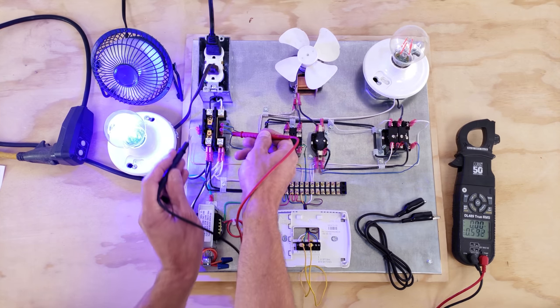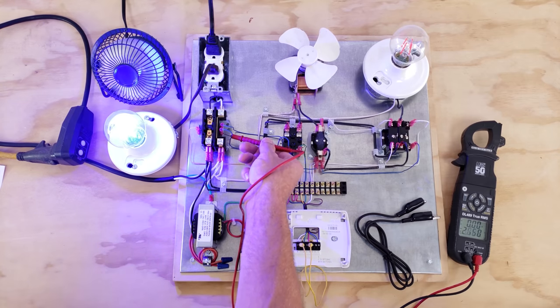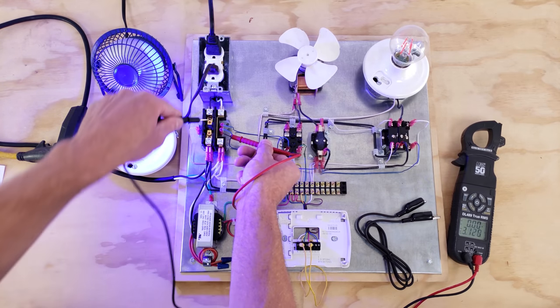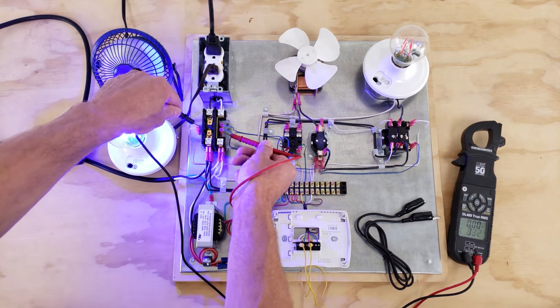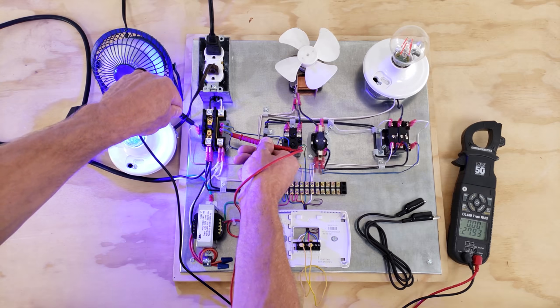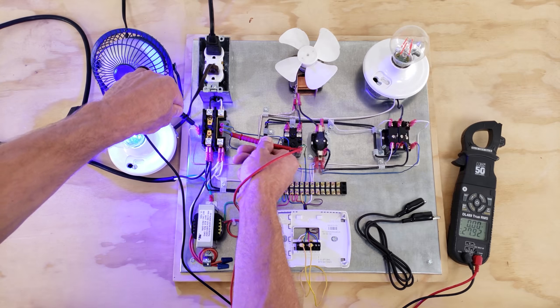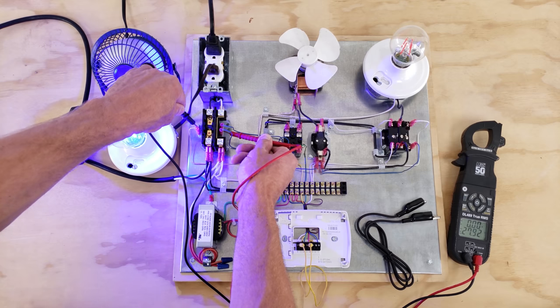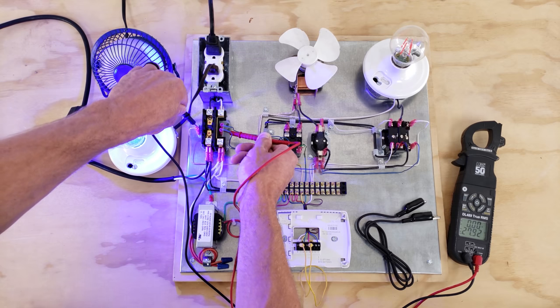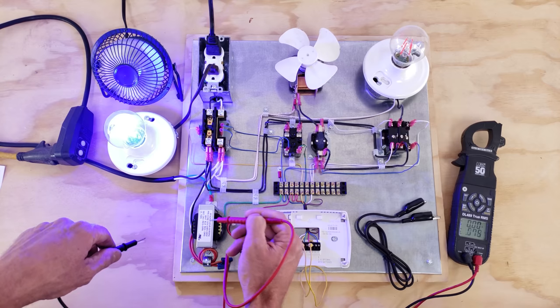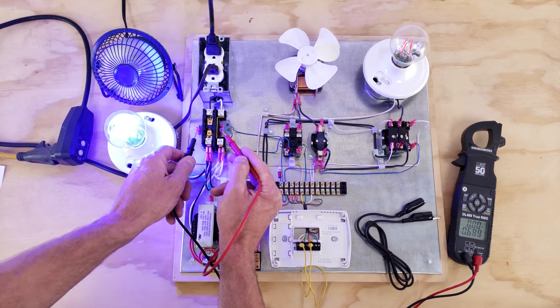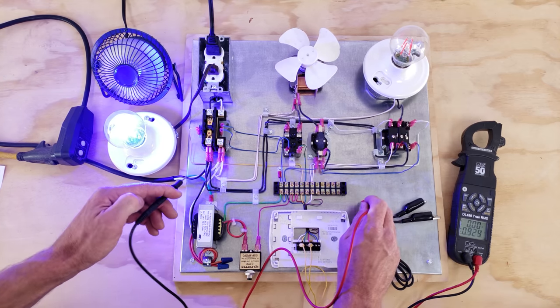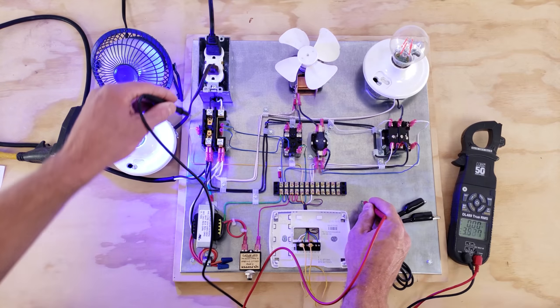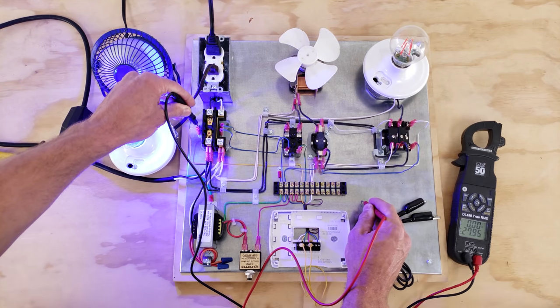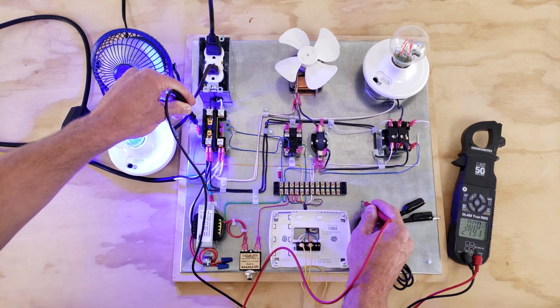And so you can check your outdoor unit contactor right between here and here. I'm trying to shuffle around because it's difficult trying to get the camera here. So we got 27 volts right there. 24 volts is actually going to be anywhere from, say, 24 to 29 and a half volts coming from the transformer right here. So you see we got 24 volts right there. Now we can just put a probe onto the ground, and then we can put one on the hot. We're going to get the same reading, our 27 volts.